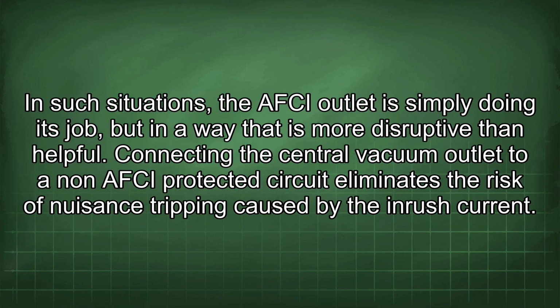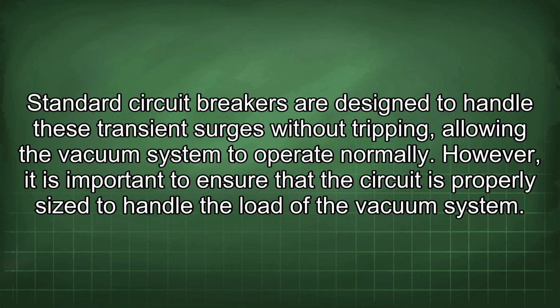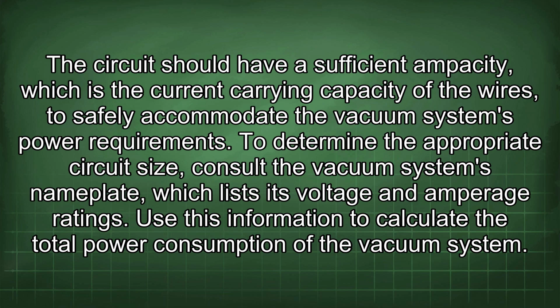In such situations, the AFCI outlet is simply doing its job, but in a way that is more disruptive than helpful. Connecting the central vacuum outlet to a non-AFCI protected circuit eliminates the risk of nuisance tripping caused by the inrush current. Standard circuit breakers are designed to handle these transient surges without tripping, allowing the vacuum system to operate normally. However, it is important to ensure that the circuit is properly sized to handle the load of the vacuum system. The circuit should have a sufficient ampacity, which is the current carrying capacity of the wires, to safely accommodate the vacuum system's power requirement.